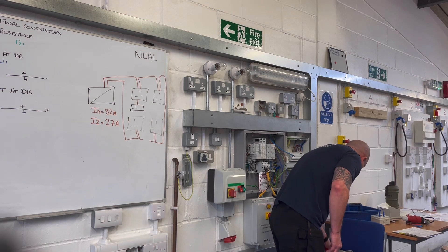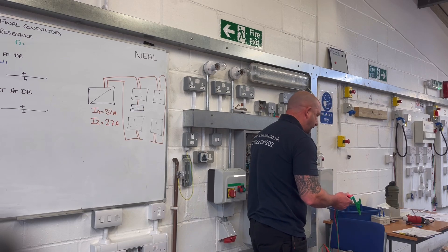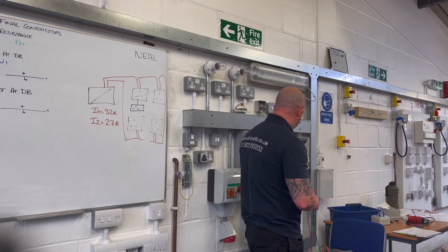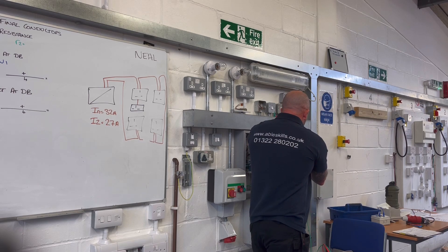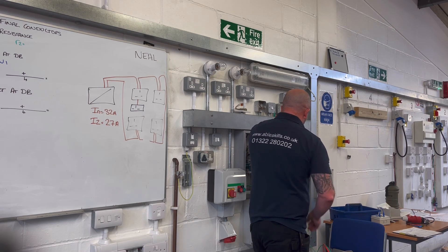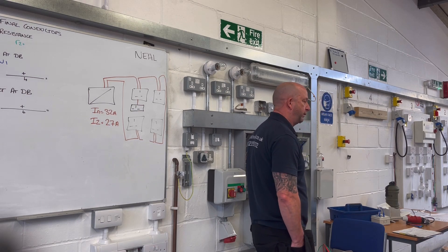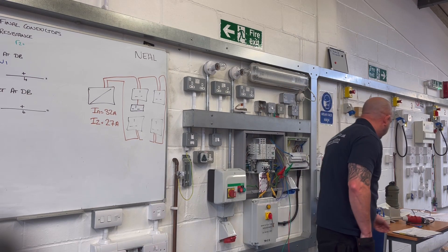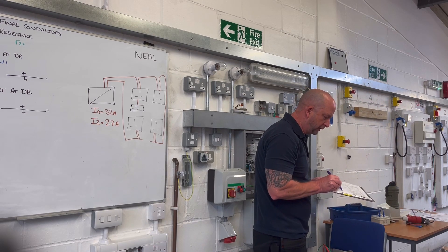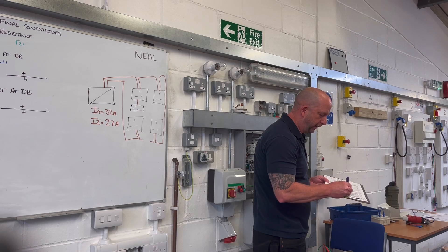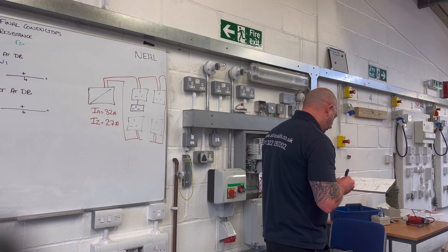The continuity tester stays set up from the previous testing — it's still zeroed, I don't need to do anything to it. So let's measure the value of little R1. It's coming in at 0.45 of an ohm. So what I do now is record that on my schedule of test results. We're in continuity, on ring final, and little R1 is coming in at 0.45 ohm.